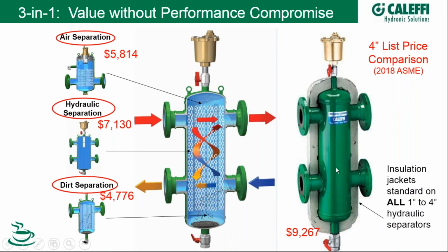And before I leave this slide, you'll see what's this here? Well, it's a half shell. It's our insulation jackets that come standard on all our smaller hydraulic separators, 4 inches and down. Very nice insulation, by the way, pretty thick, so they do a good job. There is quite a bit of surface area on the hydraulic separators, typically in your mechanical room, and so they will radiate heat and become a big heat radiator. So it's good, when possible, to insulate your hydraulic separators, because in comparison to the surface area of all the piping in your mechanical room, there might be more surface area on your hydraulic separator alone.